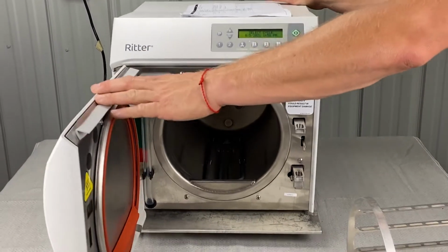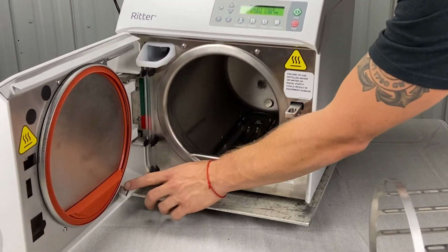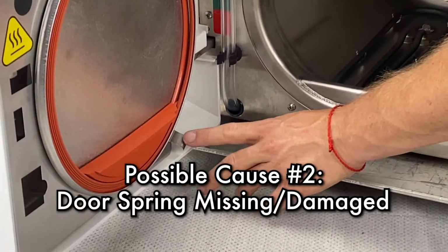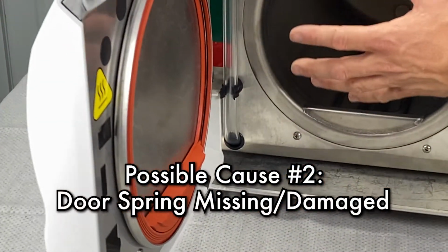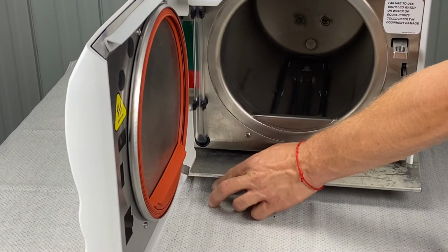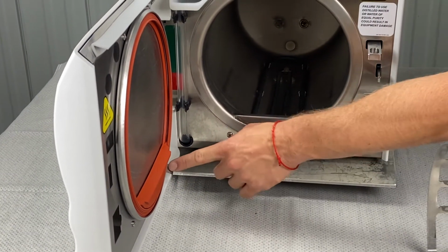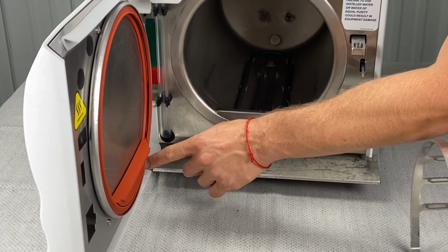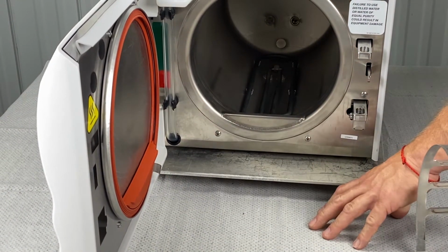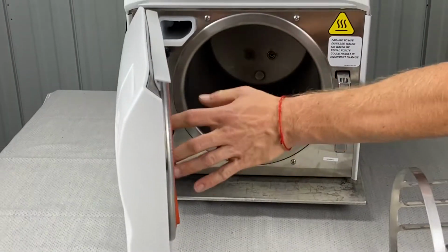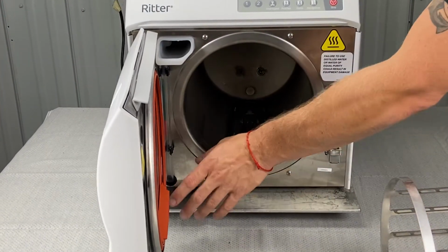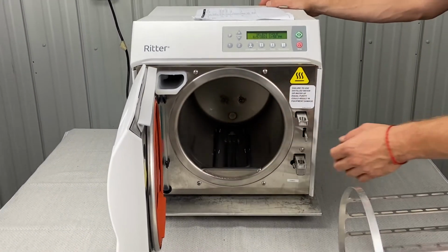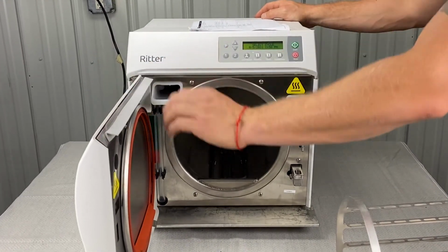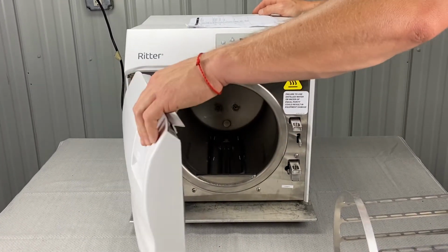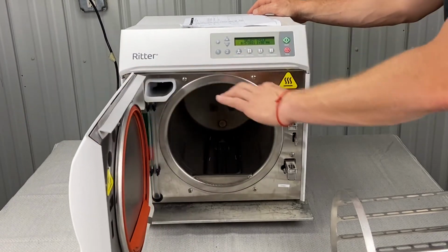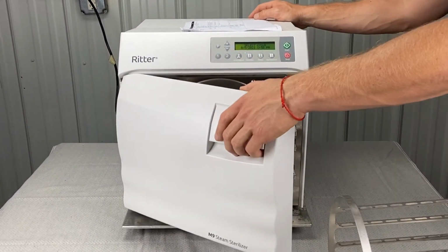While we're also there, after you open the door, you're going to want to make sure it has a door spring. This is a Midmark M9. This only has one door spring. It should be at a 45-degree angle, and it also should be put at about the 5 o'clock position. Midmark M11, which this is not, has two door springs. So you're going to want to make sure they're in place. So you're going to check the door spring, check the filters clogged, run an empty cycle, pull all your instruments out, pull all the trays out, run an empty cycle, see if the problem persists.